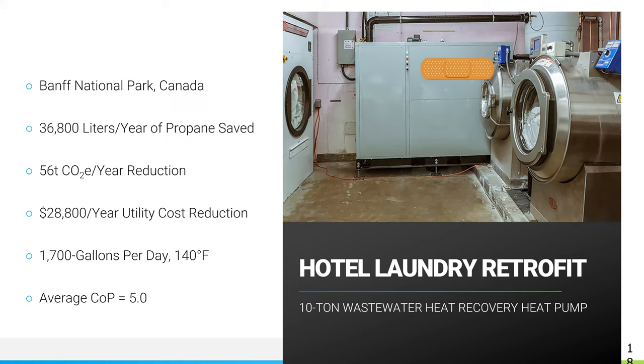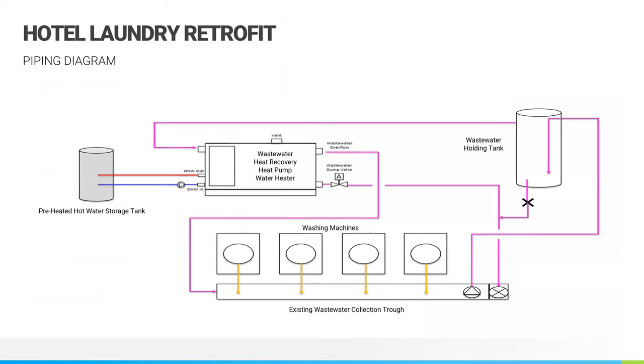in their utility costs. But the big thing here is for any type of laundry where we're just rejecting heat into an existing trough and then collecting that, the opportunity to pick that energy back up and then put it back into that laundry process is very large, and really creates a good opportunity for very super high efficiency heating, because that source water that we're taking, that source wastewater, is a warmer temperature.